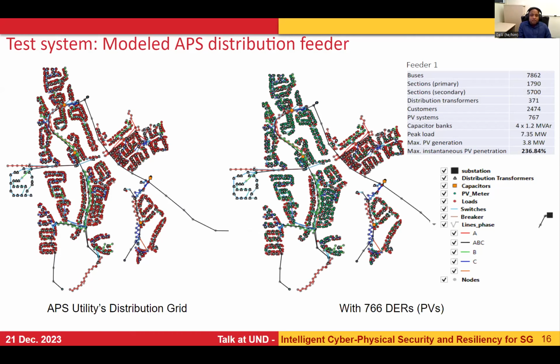On the right side, you can see the number of PV systems is 767, and we modeled 766 because the data set for one of them was not fully available. The maximum PV generation seen was 3.8 megawatts, and maximum instantaneous PV penetration was 236%, where there was reverse power flow from the DERs to the substation and sub-transmission systems level.